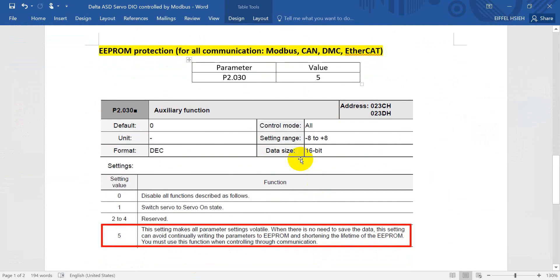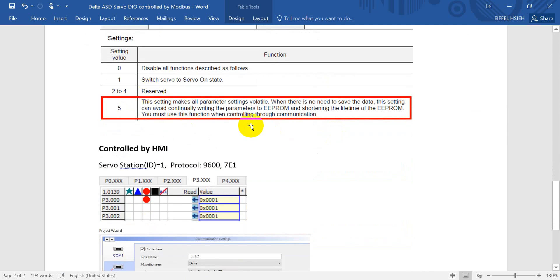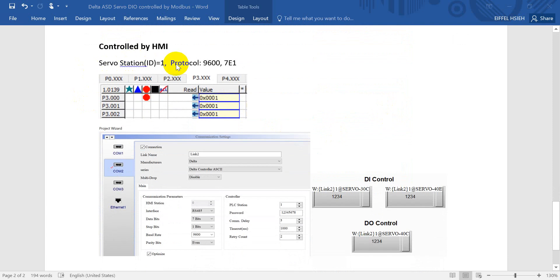Before we go further, there is one more thing that is very important. No matter whether you use Modbus, DMC net, or EtherCAT, this is a very important parameter — P2-30. We suggest you set this one to 5. The reason is: if you don't write the value to 5, then every time you modify a parameter value, you will reduce the lifetime of the EEPROM.